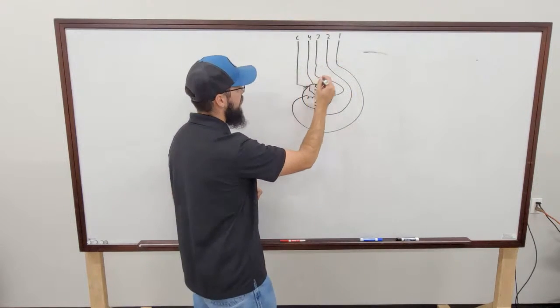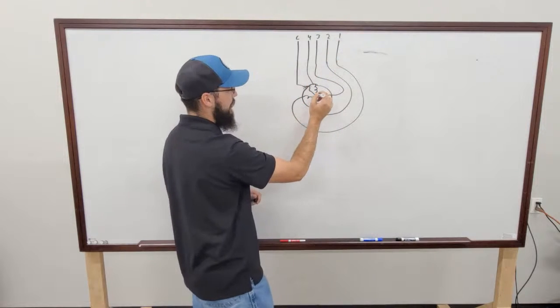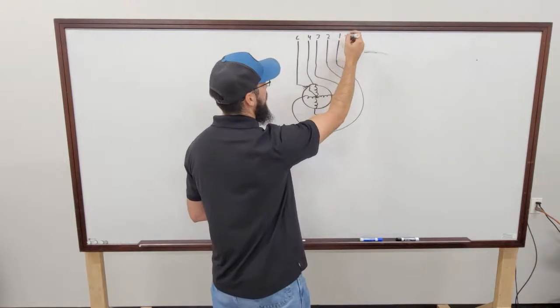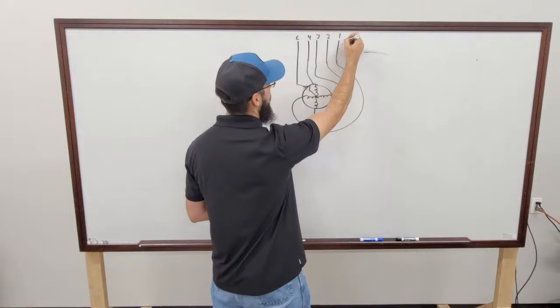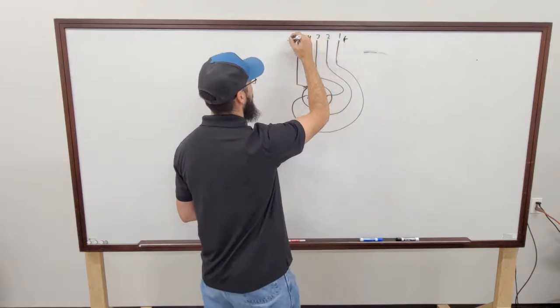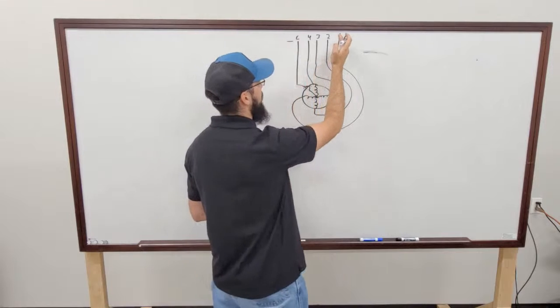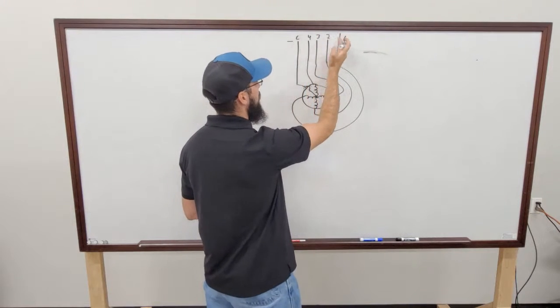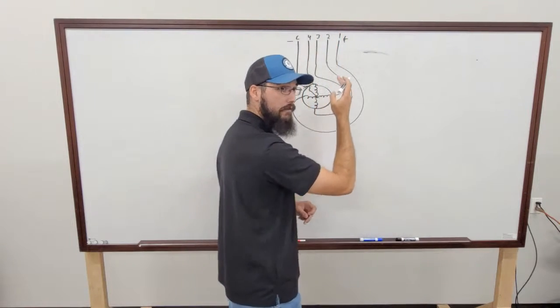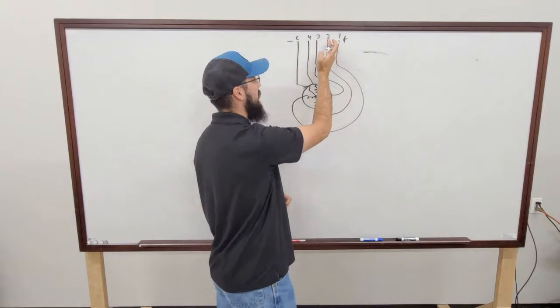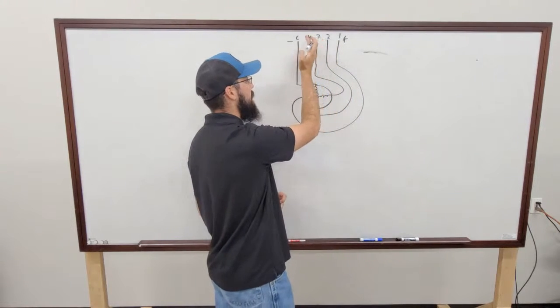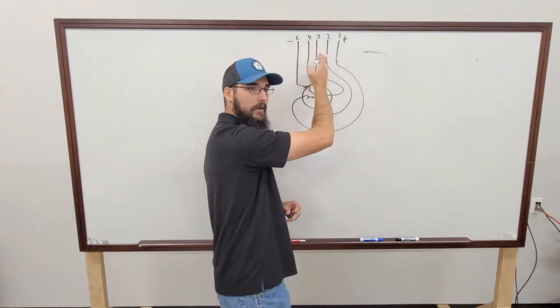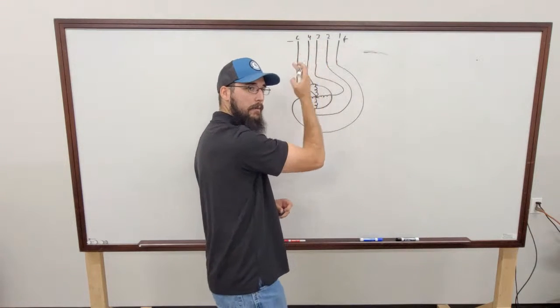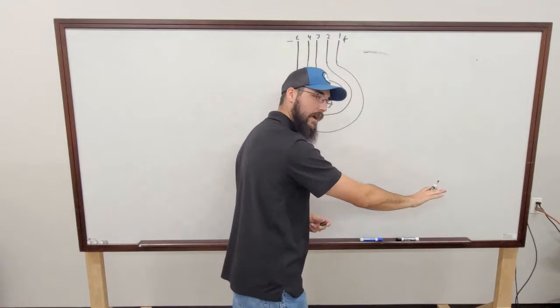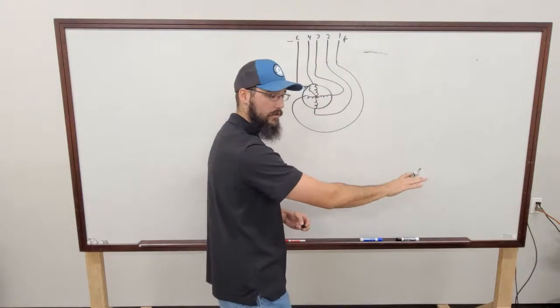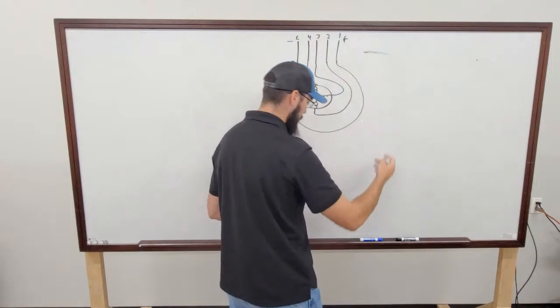And so to step this motor, we fire, so this would be initially positive, this would be a negative. So we'd go 1, 2, 3, 4, 1, 2, 3, 4, 1, 2, 3, 4. Every time we go 1 to 2, that's 1 step. 2 to 3, 2 steps. 3 to 4, 3 steps. You get the point. And we step those down, and that's going to step that valve to a closed position till it seals off. So that's to close it.